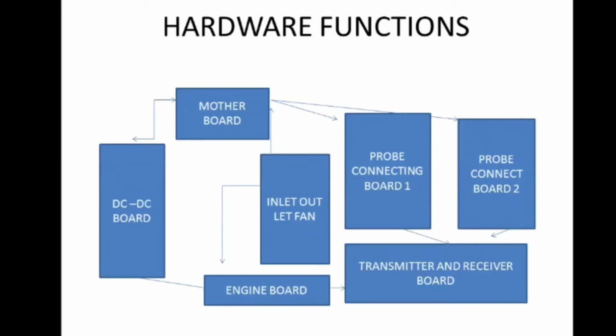So what is this probe connecting board 1 and board 2? I said a term called port, right? This port is connected directly to these hardware functions. So whenever you have to fix a probe, it will be connected towards the motherboard, and with that help you can see the entire image.